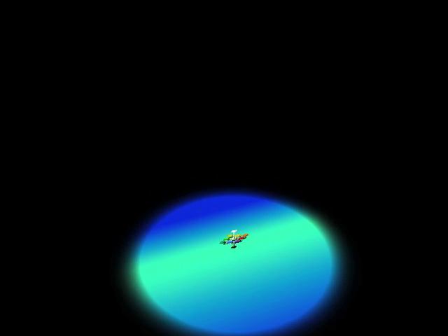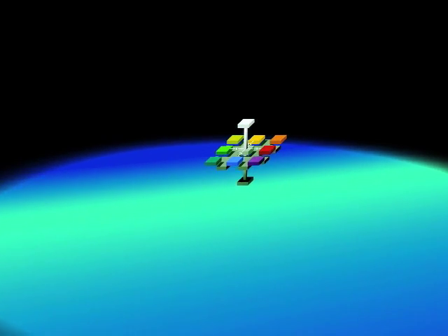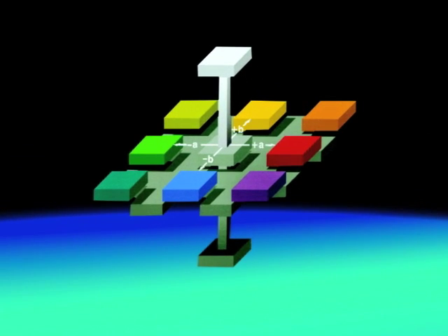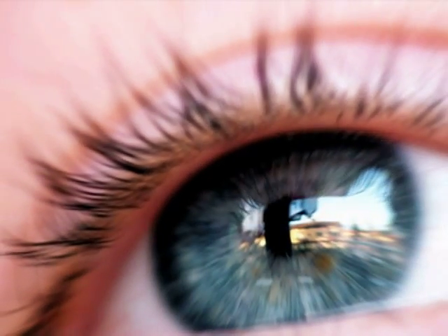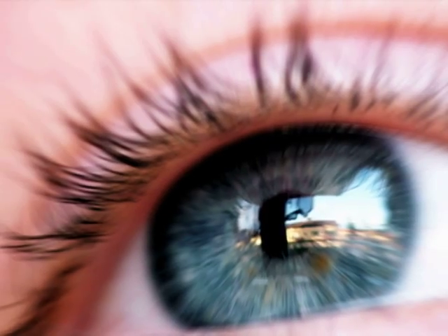Similar to our brain, the instrument uses three values to define a color. The L, or lightness value, is 0 for black and 100 for white. The A value is positive for red and negative for green. The B value is positive for yellow and negative for blue. This is called opponent color. Another way to look at it, the human eye will never see a reddish green or a bluish yellow.